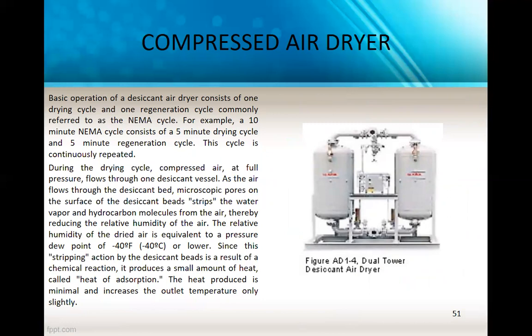Commonly referred to as NEMA cycle. For example, a 10-minute NEMA cycle consists of a 5-minute drying cycle and a 5-minute regeneration cycle. This cycle is continuously repeated.